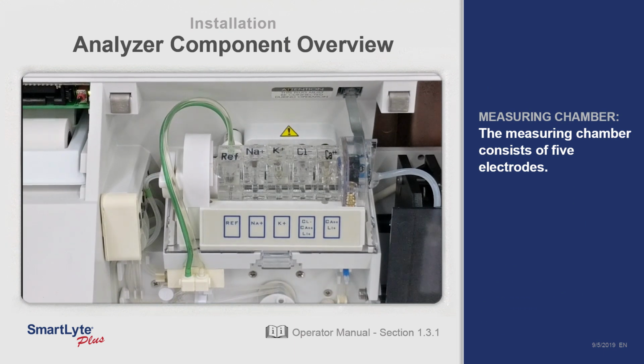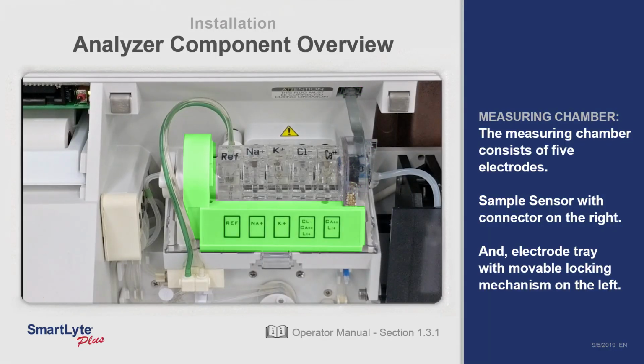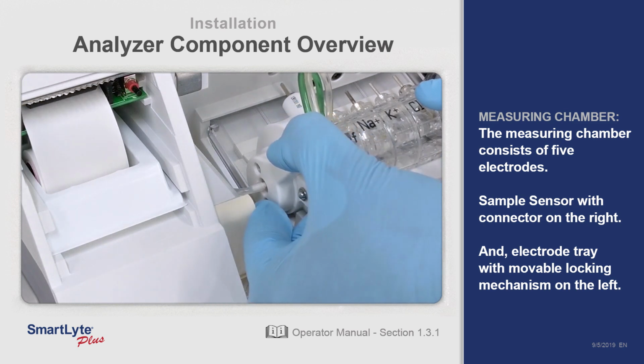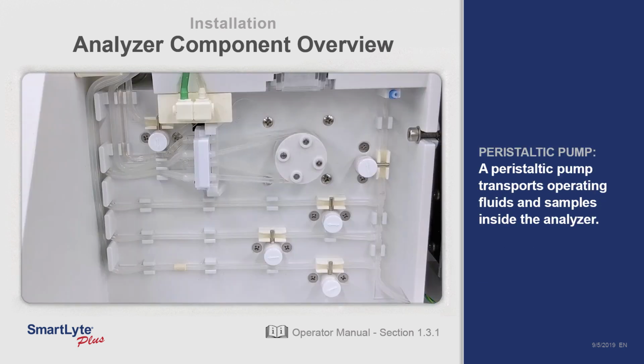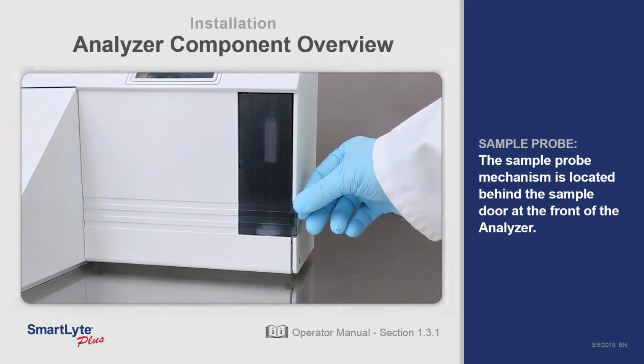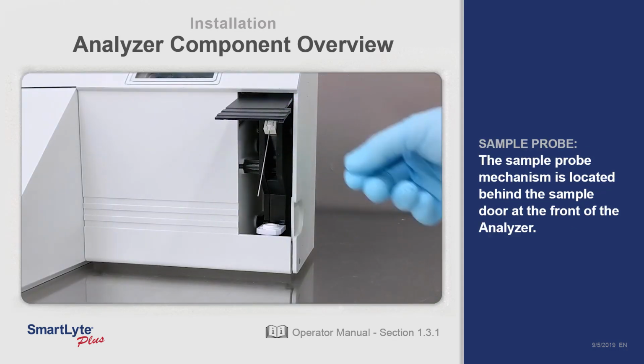Measuring chamber. The measuring chamber consists of 5 electrodes, a sample sensor with connector on the right, an electrode tray with movable locking mechanism on the left. Peristaltic pump. A peristaltic pump transports operating fluids and samples inside the analyzer. Sample probe and cover. The sample probe mechanism is located behind the sample door at the front of the unit.